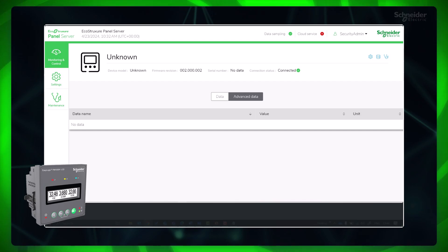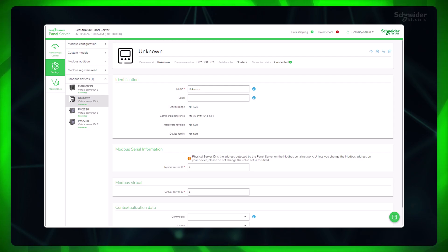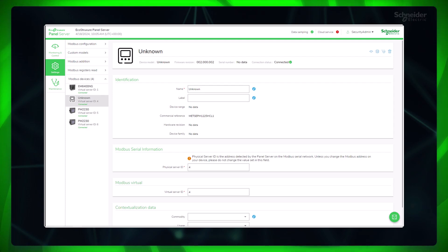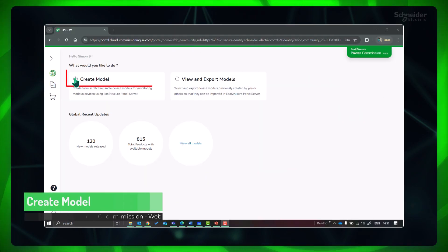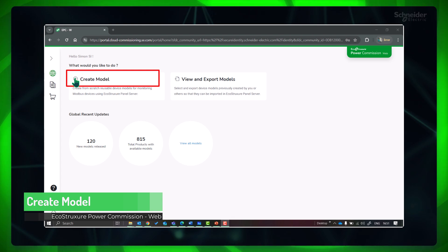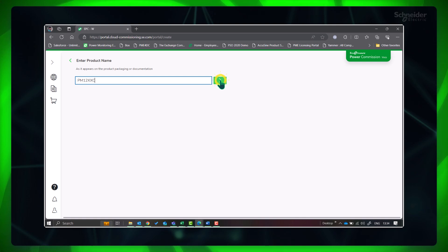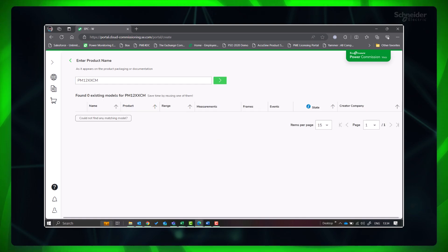To demonstrate, we are utilizing the Schneider PM 1225H meter for custom model creation, since this device isn't natively supported in Panel Server. The procedure remains consistent with any third-party Modbus meter. Click Create Model and enter the product name of the device for which you are going to create the custom model. The portal will indicate whether anyone has already created a custom model for this device.